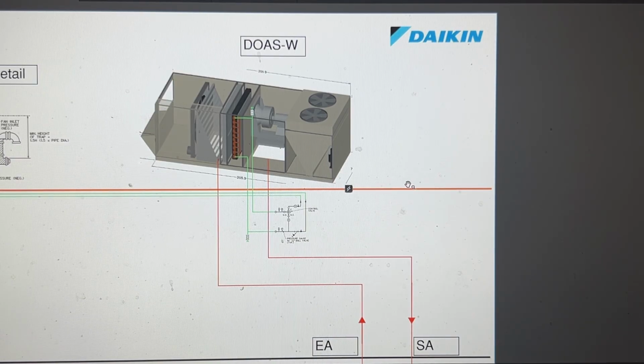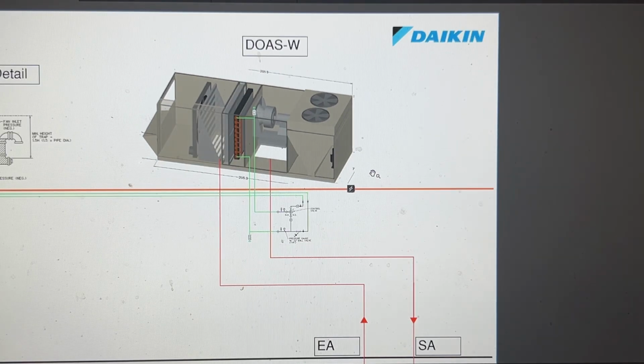So I'm just going to get into this overview. There's a DX coil inside the unit. So it's a self-contained unit, which has a refrigeration coil within it, which tempers the air in the hot seasons here. So that refrigeration coil will cool it down before it pushes it to the floors. And conversely, there's a hot water reheat coil that does the same thing to temper when we're in colder conditions. So the hot water coil is glycol based.